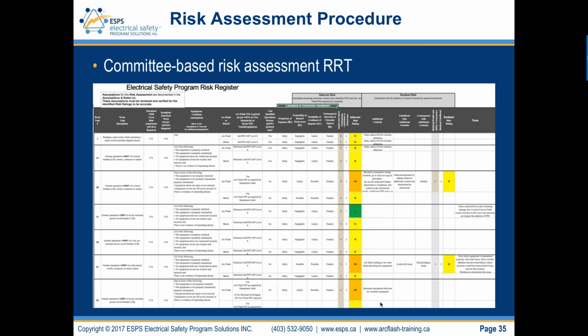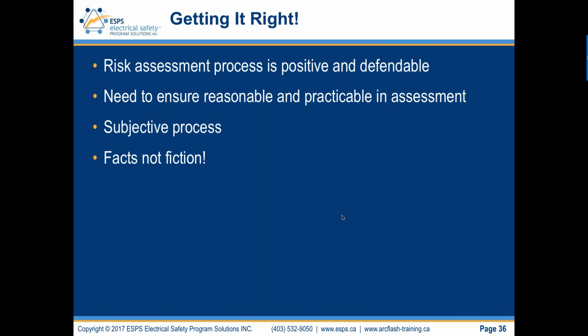So this is an example of a committee-based risk register table. Basically the work tasks that are listed on the left come right out of NFPA 70E and Z462. But then you apply an inherent or initial risk assessment, and then you apply controls to reduce the residual risk, and you put some different risk levels on it. It could be low, medium, high, or 1, 2, 3, 4. Depends on, again, the specific matrix that's developed by the company implementing it, or they may have an existing risk assessment procedure and risk assessment matrix that can be applied as well in alignment with the risk assessment procedure in 70E and Z462. So getting it right.